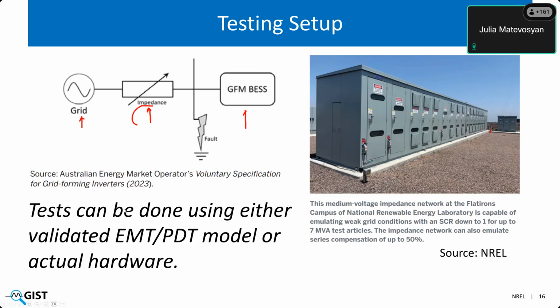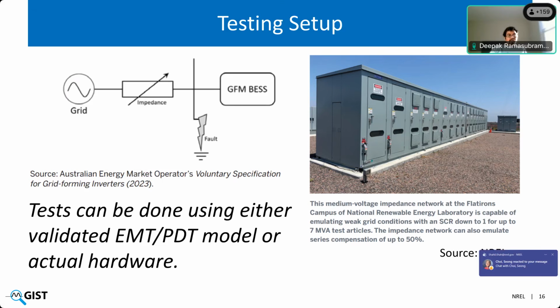Right. The next question is, given that the phasor domain transient model is valid up to 40 hertz and most are not valid above 4 hertz, is it really possible to use phasor domain transient models to test the proposed grid forming criteria? Yeah. So it's a mixed response here, right? The idea is not to say that the phasor domain model can be used up to 40 hertz. It's definitely also not the case that the phasor domain model is not valid above 4 hertz. In fact, there are very good phasor domain models that many OEMs have developed that are valid up to around 9 to 10 hertz. So what we do with this approach is that, to a certain extent, especially if you're looking up to the bandwidth of phasor domain software, we can get an understanding of the grid forming property, but we can't get the full range.